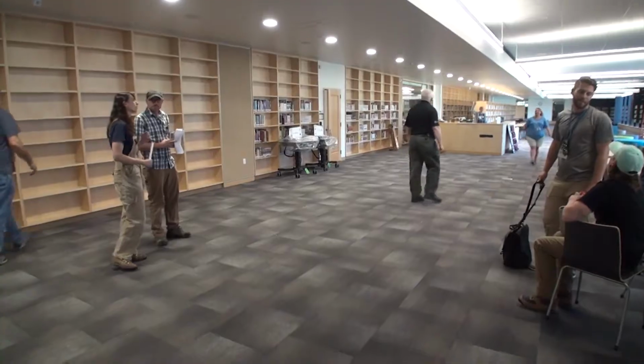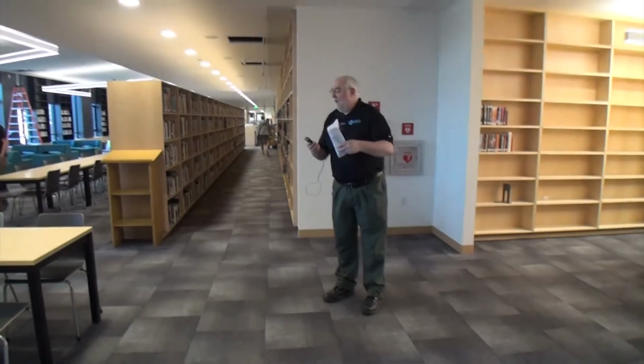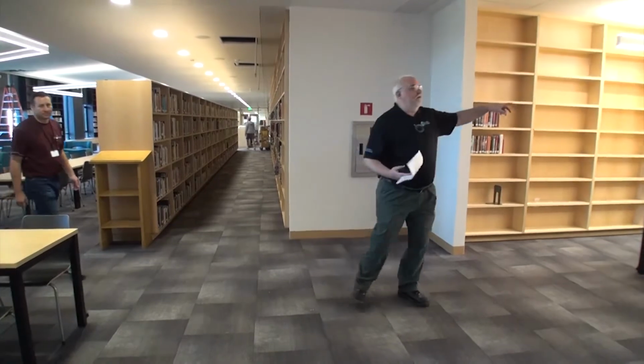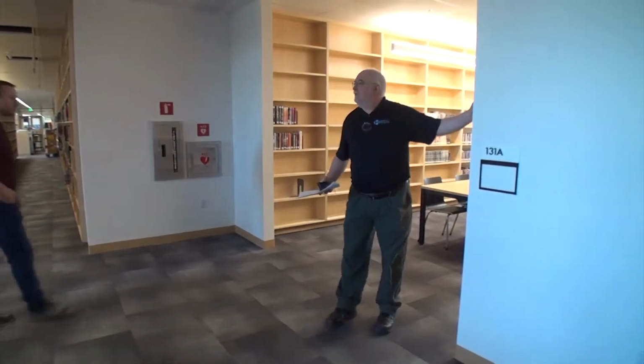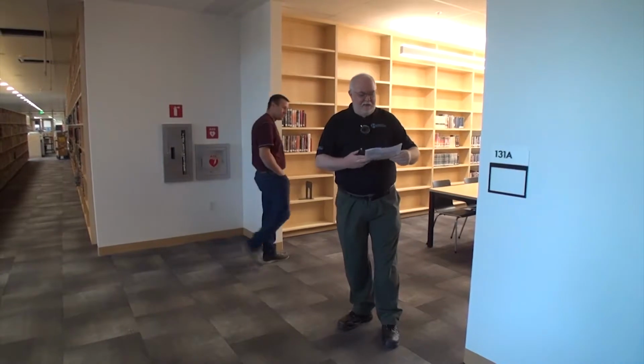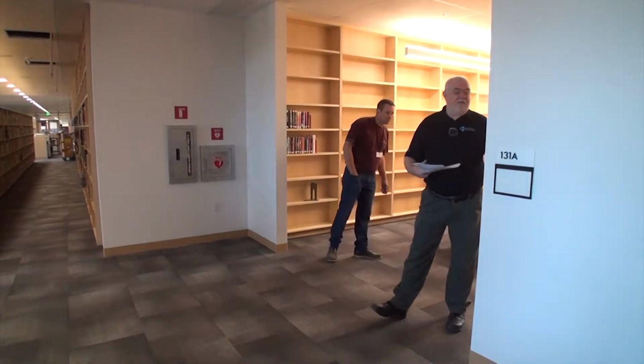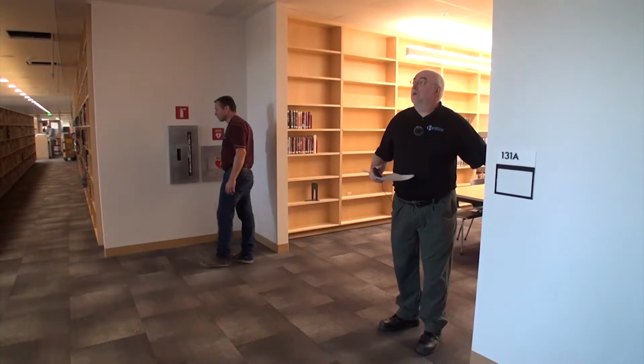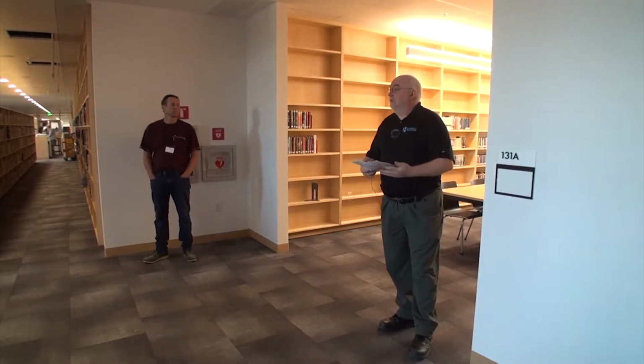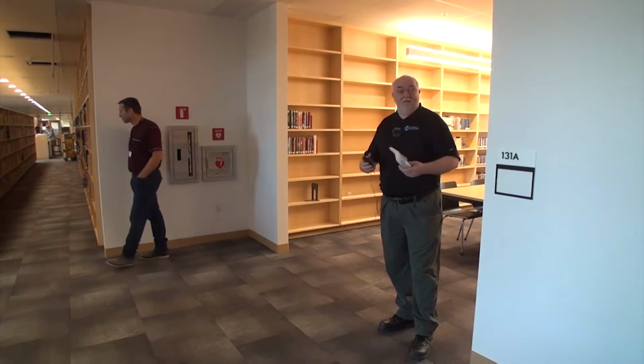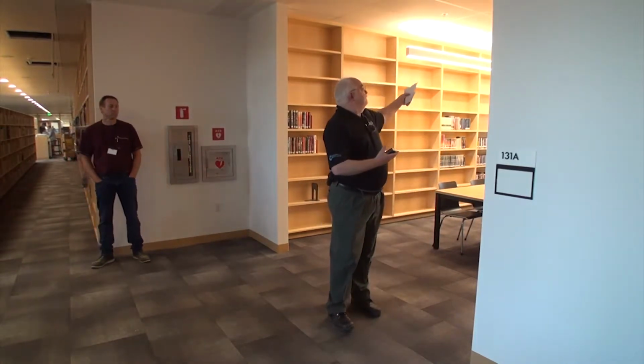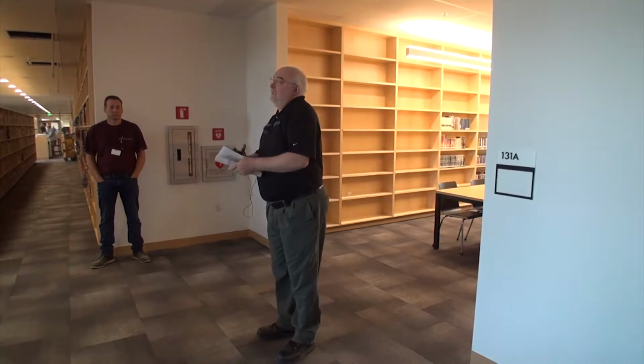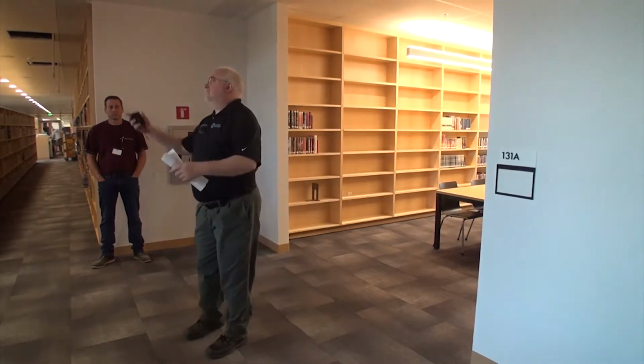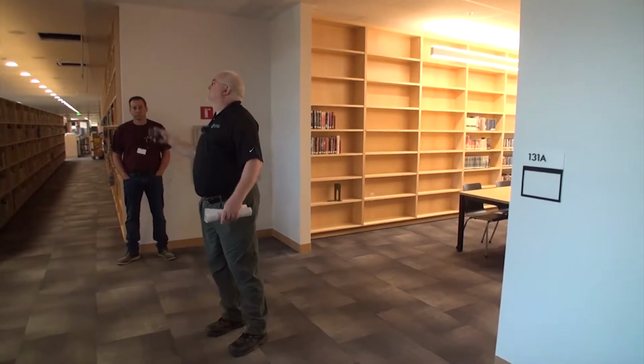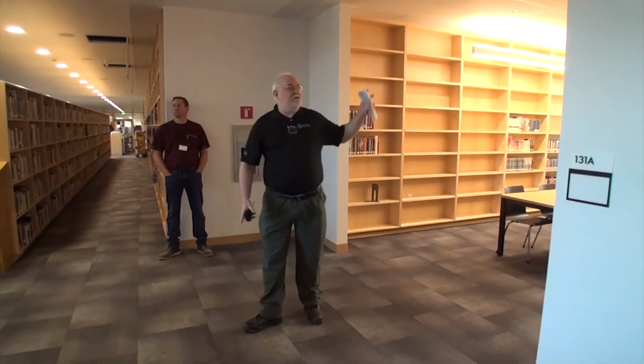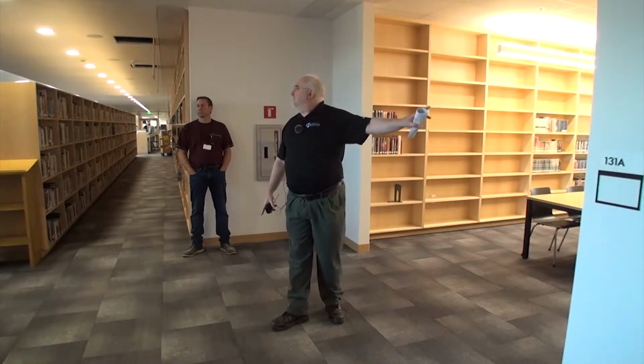Yeah, I did have a question. So just FYI, although this looks like it's part of the library, lighting-wise it's an independent zone. I believe we have this set up as an office, which means you have to turn the light switch on, and it'll go off automatically. So it's semi-auto for this one, 15 minutes. It has an occupancy sensor to tell you whether or not there's anybody in the room. The difference between this space and the one you're standing in is that this is networked and runs off the time clock, the 6 to 6, whereas this is an independent zone all on its own.